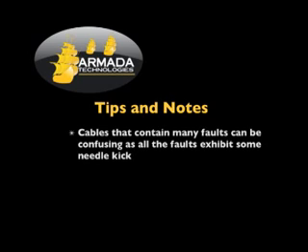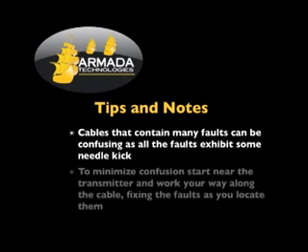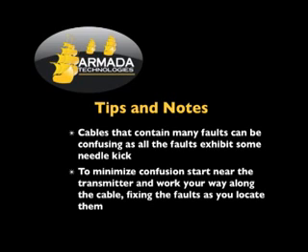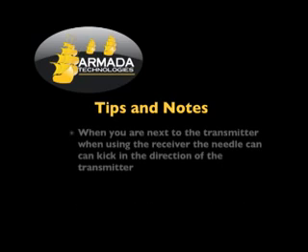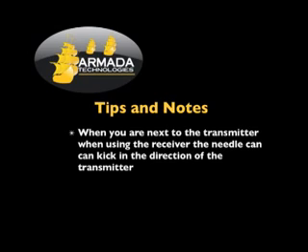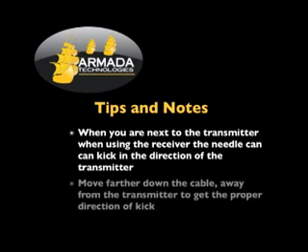Cables that contain many faults can be confusing as all the faults exhibit some needle kick. To minimize confusion, start near the transmitter and work your way along the cable, fixing the faults as you locate them. If you are next to the transmitter when using the receiver, the needle can kick in the direction of the transmitter. Move further down the cable, away from the transmitter, to get the proper direction of kick.